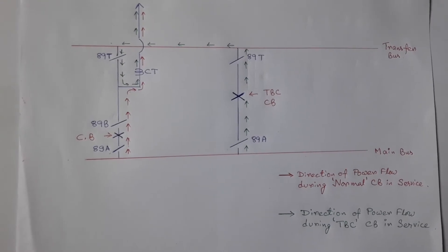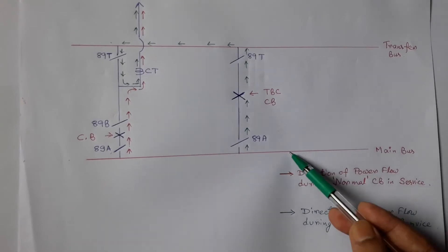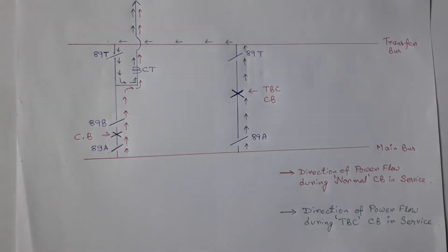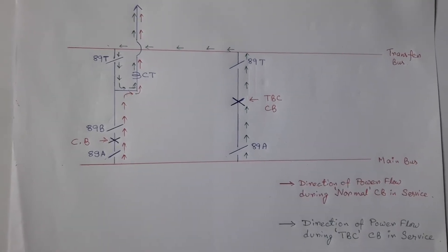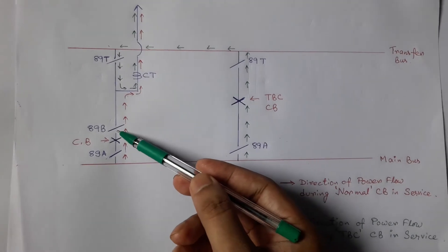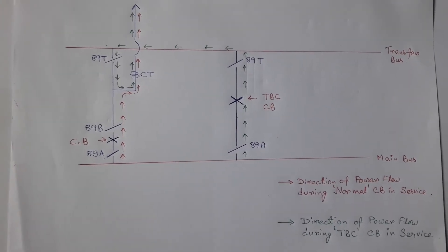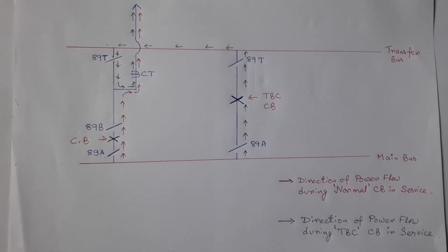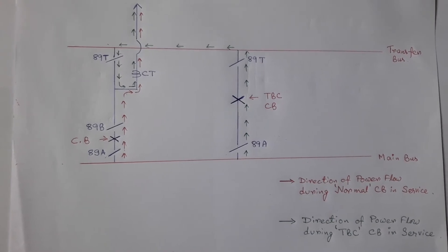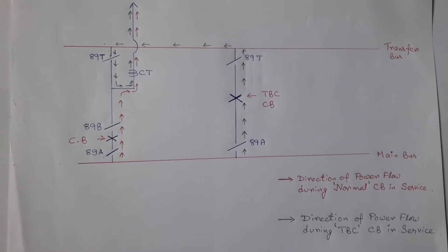What is a TTS switch? It's a trip transfer switch, used in a substation where there is one main and one transfer bus, and the CT is connected on the line side. If the CT is connected on the bus side, then the trip transfer switch is not required. You can comment on what are the advantages and disadvantages of a line side CT.